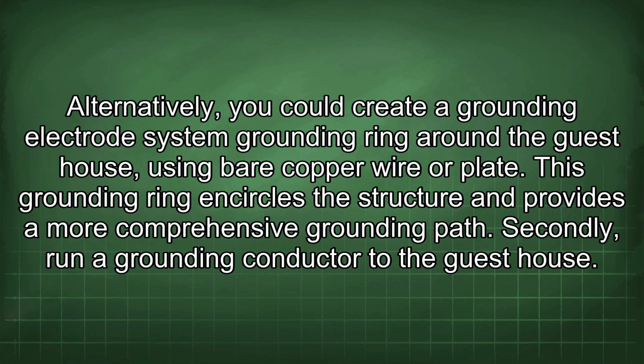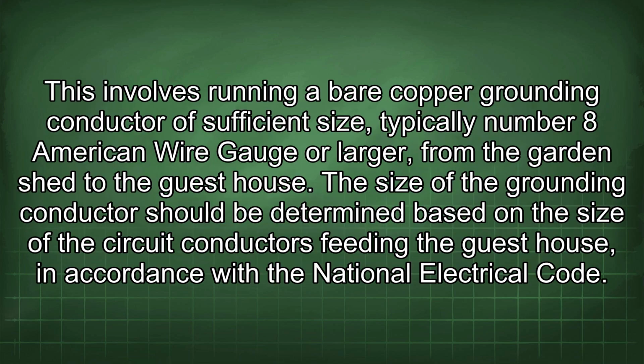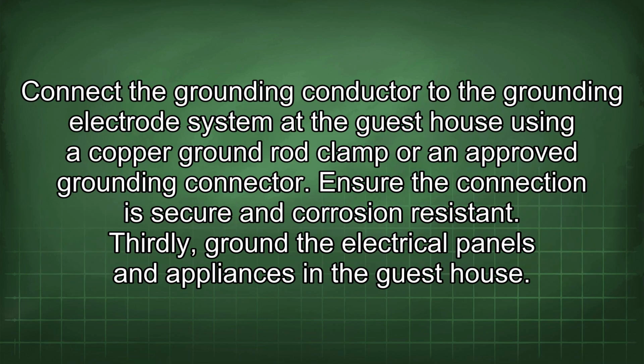Secondly, run a grounding conductor to the guest house. This involves running a bare copper grounding conductor of sufficient size, typically number 8 American wire gauge or larger, from the garden shed to the guest house. The size of the grounding conductor should be determined based on the size of the circuit conductors feeding the guest house, in accordance with the National Electrical Code. Connect the grounding conductor to the grounding electrode system at the guest house using a copper ground rod clamp or an approved grounding connector. Ensure the connection is secure and corrosion resistant.